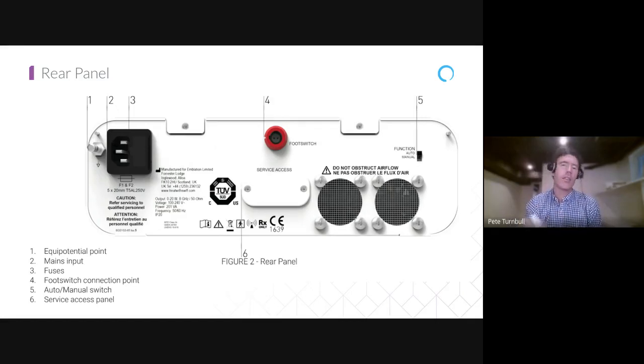Just check the back of the system, because it's in auto. If I ever get a phone call, sometimes it's like, "Pete, I don't know what's going on. When I press it, the system is just not giving energy." It's almost always the fact that it had been switched down to manual. Just so you're clear, that happens maybe once every 3 months or something. I get a phone call. So not common, but if it is going to happen, it's because that thing's been bumped somehow.